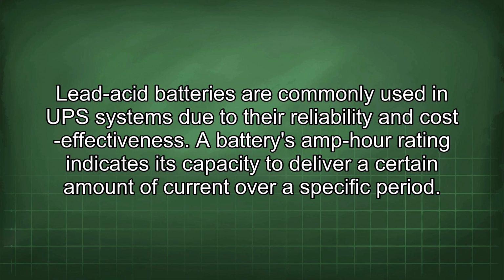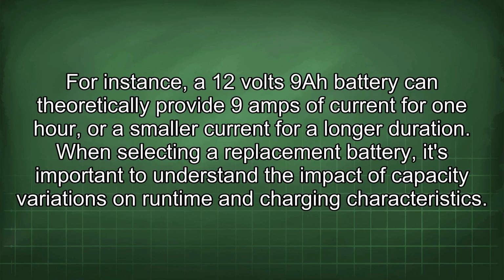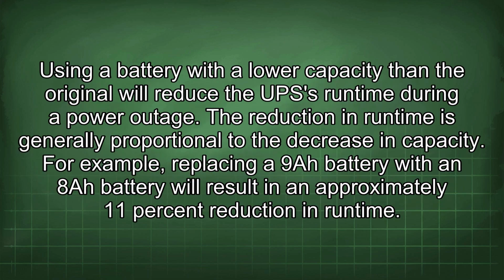A battery's amp-hour rating indicates its capacity to deliver a certain amount of current over a specific period. For instance, a 12 volts 9 Ah battery can theoretically provide 9 amps of current for 1 hour, or a smaller current for a longer duration. When selecting a replacement battery, it's important to understand the impact of capacity variations on runtime and charging characteristics. Using a battery with a lower capacity than the original will reduce the UPS runtime during a power outage. The reduction in runtime is generally proportional to the decrease in capacity.